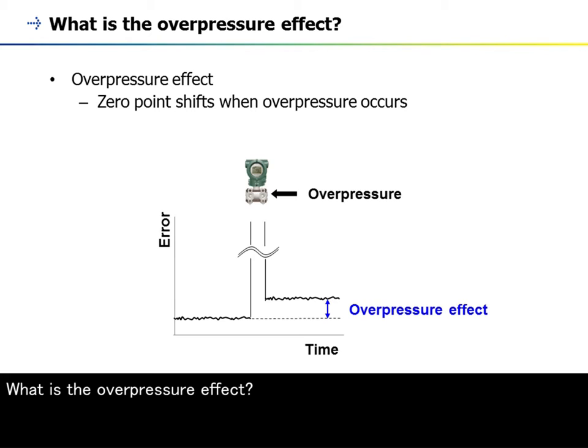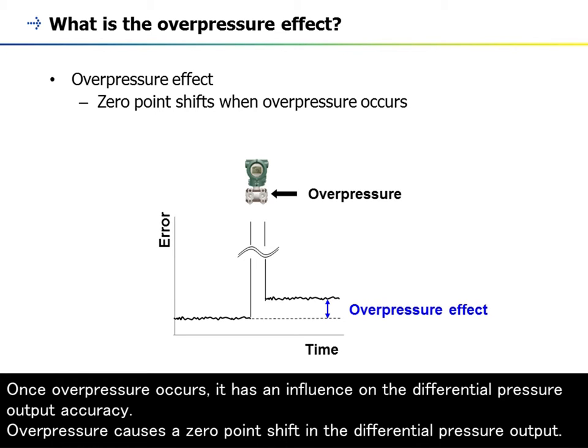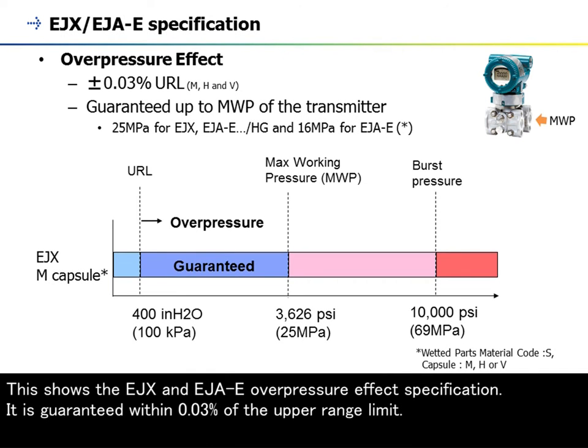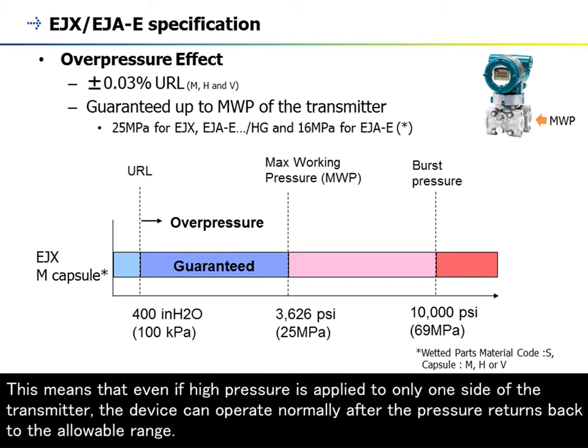What is the overpressure effect? Once overpressure occurs, it has an influence on the differential pressure output accuracy. Overpressure causes a zero-point shift in the differential pressure output. This shows the EJX and EJAE overpressure effect specification. It is guaranteed within 0.03% of the upper range limit, meaning that even if high pressure is applied to only one side of the transmitter, the device can operate normally after the pressure returns back to the allowable range.